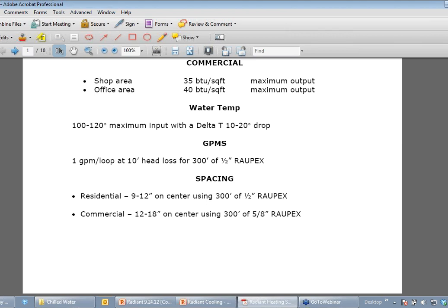Commercial, as a rule of thumb, we tend to use a little bit larger pipe than we do residentially. We tend to use 5/8 inch pipe instead of half-inch, and we tend to space it a little bit more. Residentially, we space them a little bit closer, which dictates the smaller pipe. We space them a little bit closer because people are typically walking around barefoot and things like that.